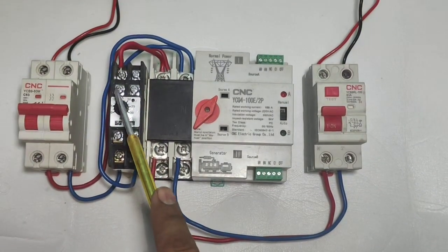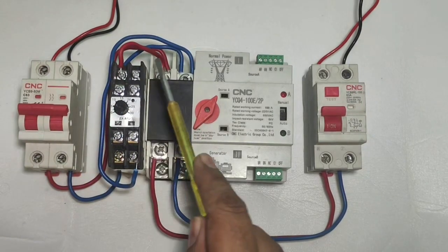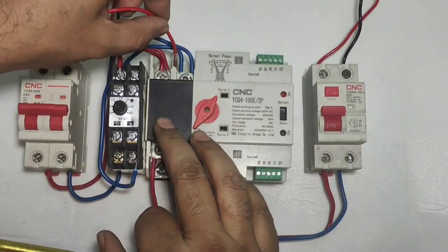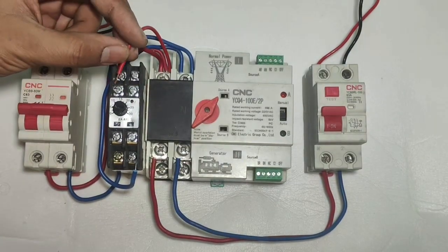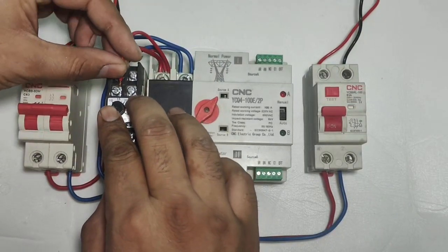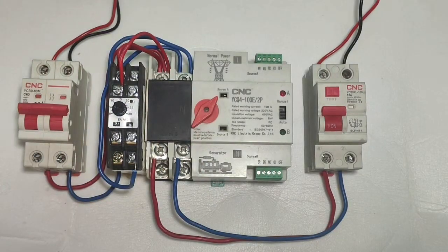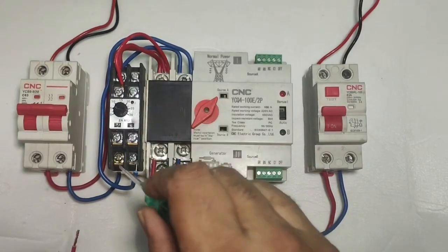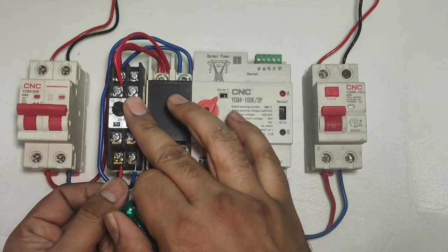Okay, and we also connect one main power supply connector to the timer common terminal. You can connect it here, also from the MCB output. So we connect one connector and connect this line wire to the timer common point, which is point 15. That means the normal main power supply line wire always comes here, and after 5 seconds, the delay you set in this timer, its supply comes on the NO point.